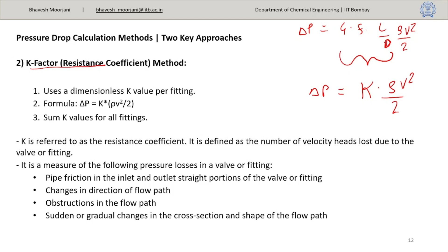And then the second method is the K factor method, or resistance coefficient method. Actually, both methods, the equivalent length method and the K factor method, are related. In the Darcy-Weisbach equation, delta P is equal to 4 times f L by D times rho V square by 2, right? So if we convert this, rho V square by 2 represents the pressure head, right? So this friction factor times L by D we represent as a constant K. That is nothing but your K method, where pressure drop is calculated as K times rho V square by 2, right? In this method, we have to find the K value for all the fittings.